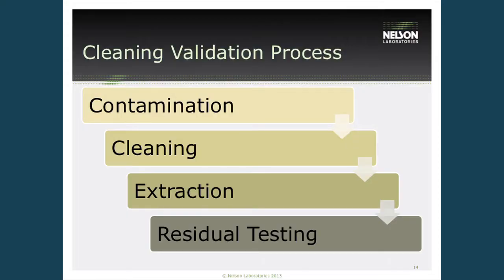So basically the 4 steps in a cleaning validation are the contamination, which equals the surgical procedure, the cleaning, the extraction of the device to get everything off of it, and the residual testing to make sure it was clean.